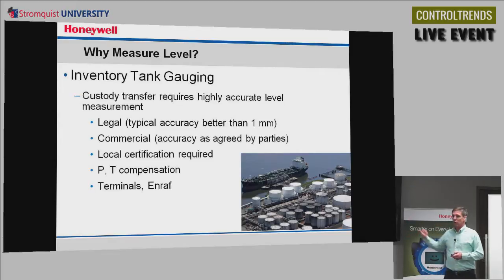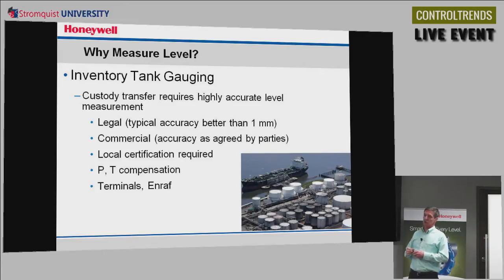And when we're talking about inventory tank gauging, we're talking about accuracies of plus or minus 1 millimeter. Remember when we talked about our level gauge, we're talking about plus or minus 3 millimeters for process kind of application. So here we're looking for plus or minus 1 millimeter. And to get that, we'll do some sort of pressure and temperature compensation. And these devices, when it comes to radar level, are typically 4-wire devices, meaning there's 2 wires for power and 2 wires for signal. Our process gauge is going to be a 2-wire device. And these are typically more expensive than our process gauge. So because accuracy is so important, people are going to pay a little bit more.